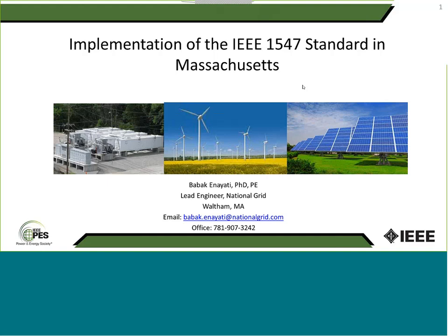So today Babak will present a brief overview of the IEEE 1547 standard, which governs the interconnection of devices to the distribution system. With the rapid expansion of DER in markets all over the world, there's intense interest in the most recent version of IEEE 1547, which was approved earlier this year. The previous version of this standard dated from 2003, and a lot of change has happened since then. So we'll focus on the new standard, particularly concerning the new requirements for voltage and frequency ride-through, frequency control, and steady-state voltage regulation.